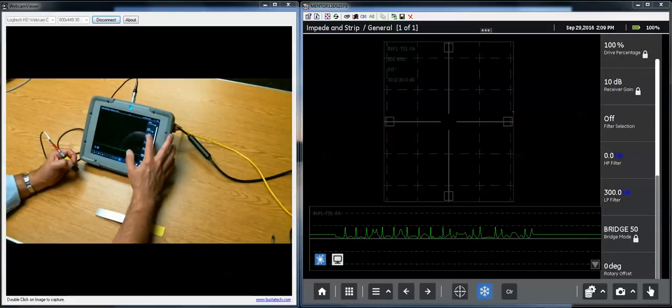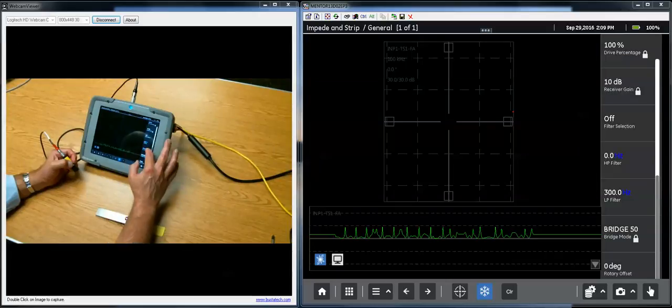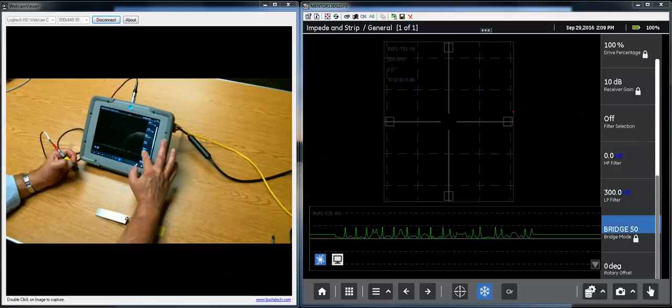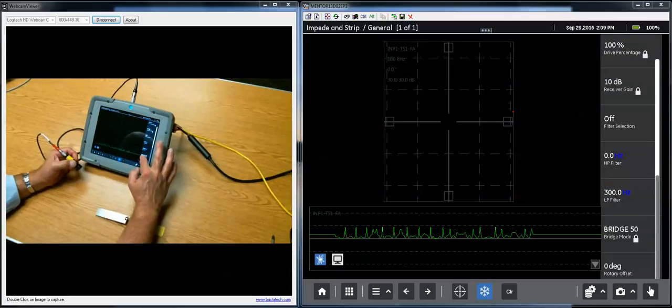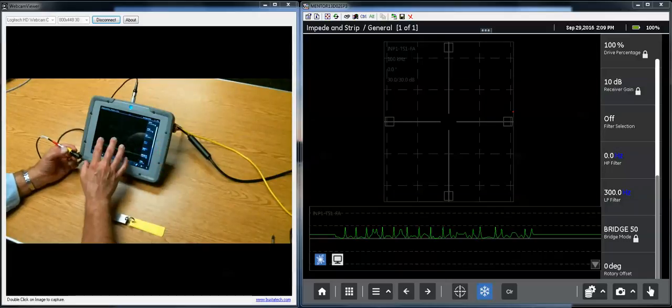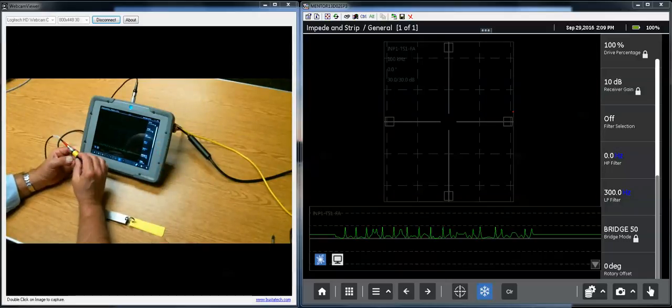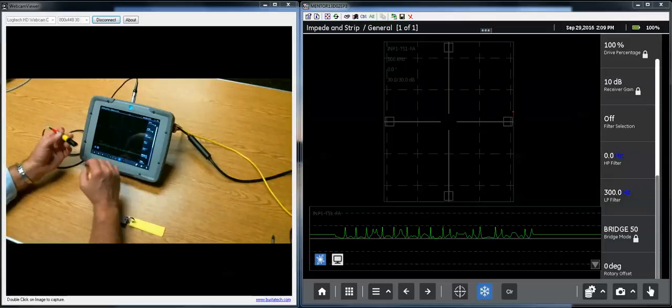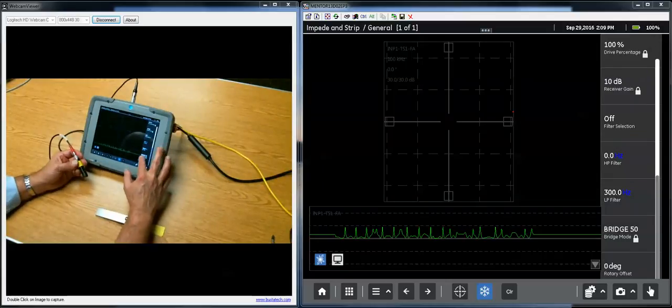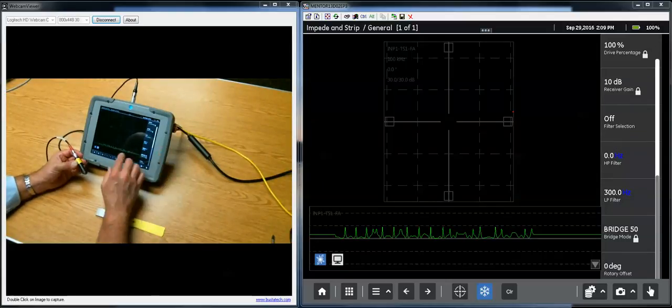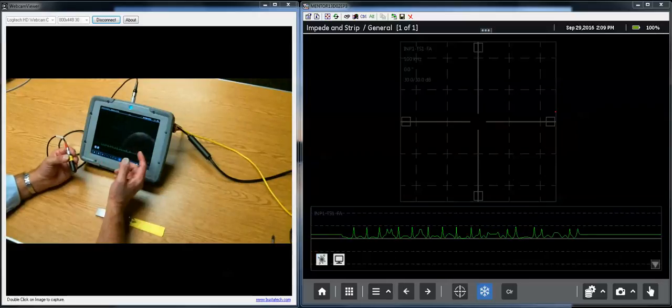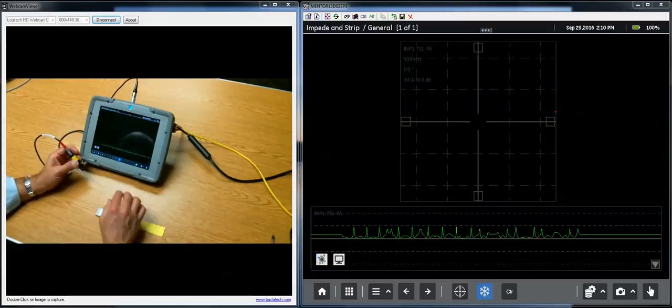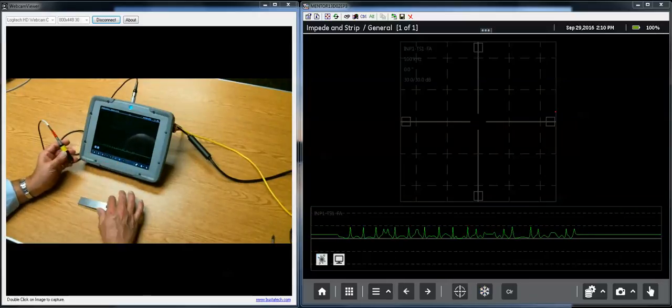Filters. You have a choice of off or band pass filter, and then you have the high pass and low pass settings for that. Bridge mode goes to how we're driving, how we set up the instrument, its generators and amplifiers with the Wheatstone bridge on the front end of the instrument, the interface to the probes. And the rotary offset we're not going to use in this application. That's only used with the rotary drive.